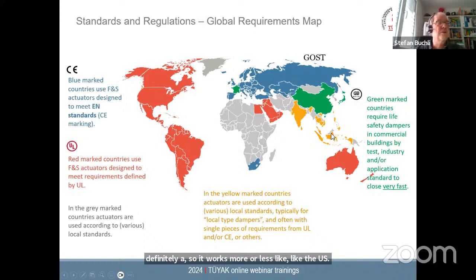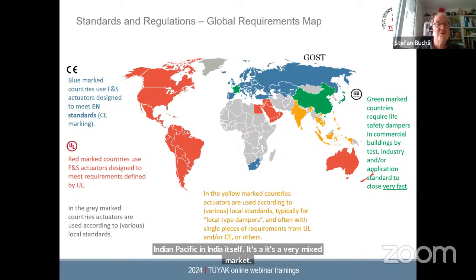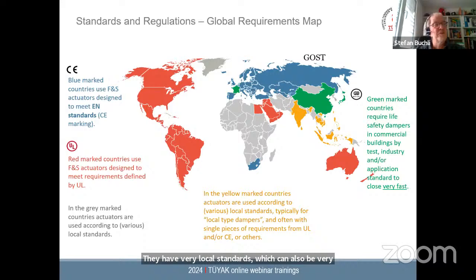Other countries, for example, if you look to the Indo-Pacific, India itself, it's a very mixed market. They have very local standards, which can also be very different. Some of the local standards, they take bits out of the UL standard, bits out of the CE standard. So it's a really mixed world there. In China and also France, you see the green part here. That's quite interesting. They have somehow a little bit of similarity because they require solutions, especially for the fire damper side, with very quick closing times. In France, they still use their NF standards, their French standards, although France is a European country. And in China, they have the so-called GB standards, which are Chinese standards. So this is a rough overview.